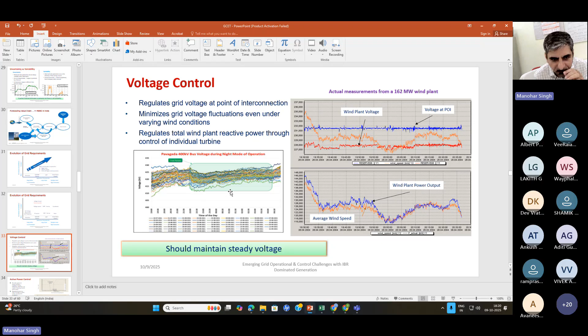This actual slide has been captured from a power plant in Karnataka, showing the Pavagada 400 kV bus voltage profile. You can see how the voltage profile fluctuates during the night. This can only be regulated with dedicated voltage control devices at the other end, or by using night mode type operations.